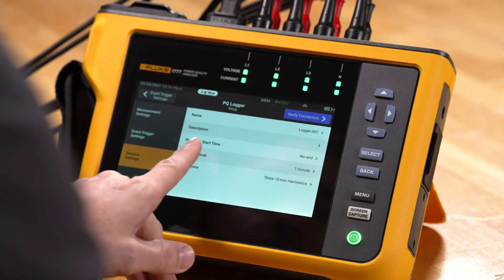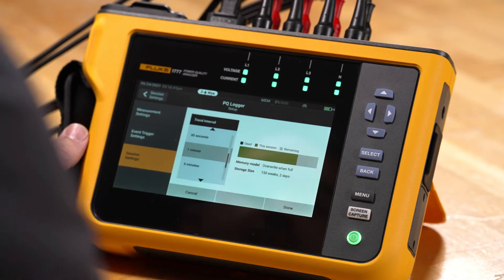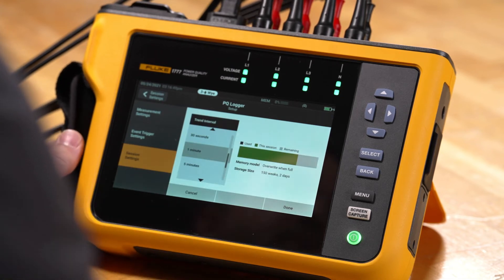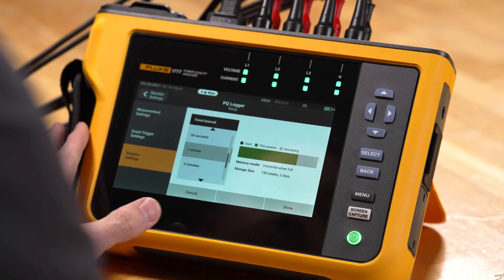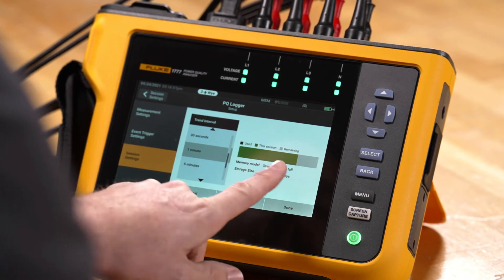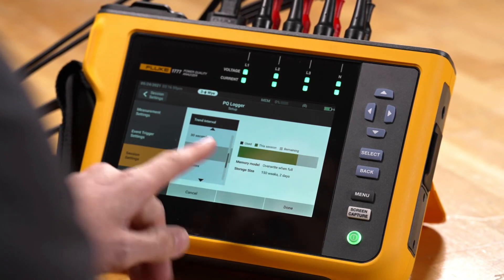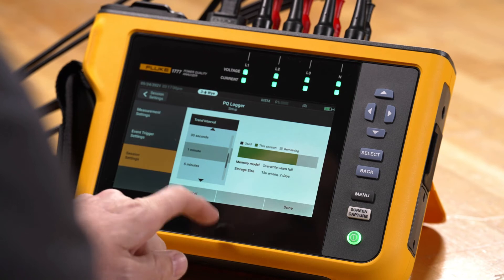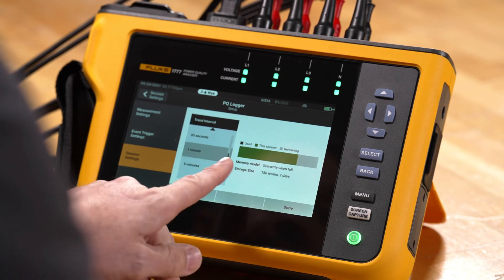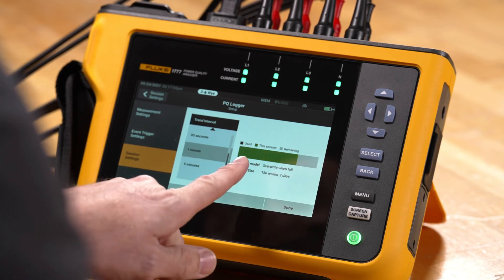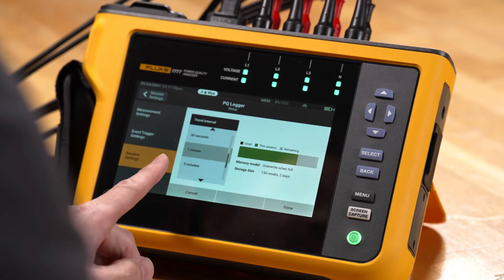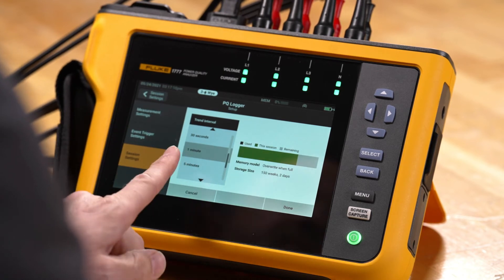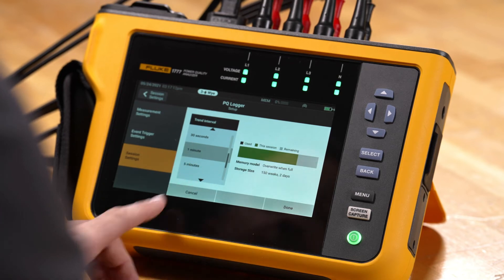We also have trend interval, which ties into the resolution of the trending data itself — that's the min, max, and average trend data. The trend interval here is one minute, but we can set it as low as one second or increase it to extend the length of recording time. This setting doesn't affect your event capture — events are still captured when they happen.